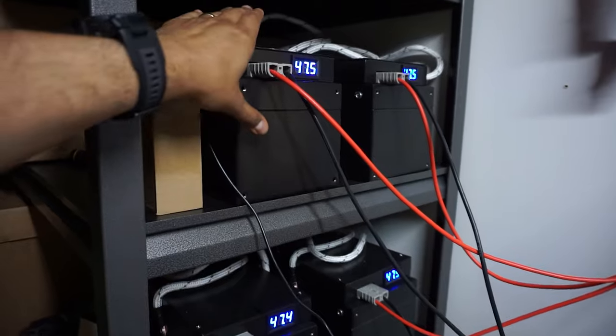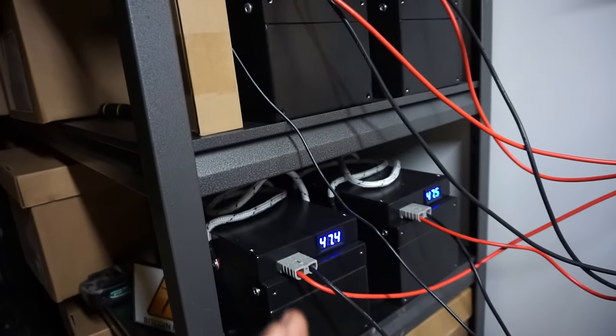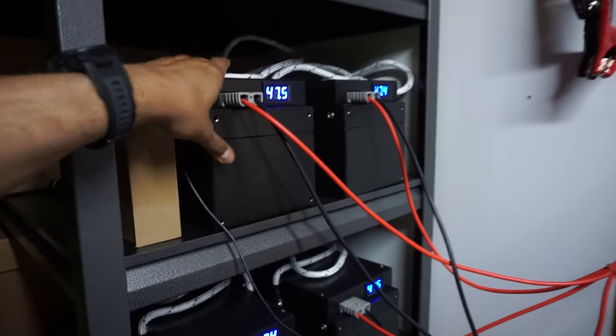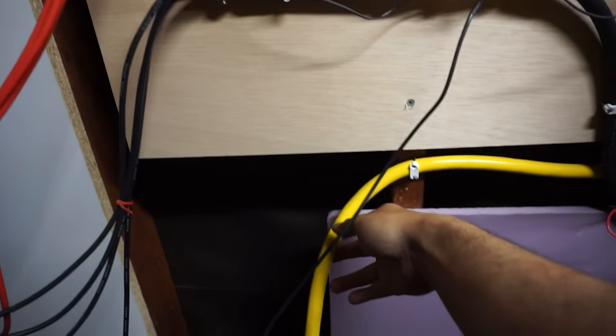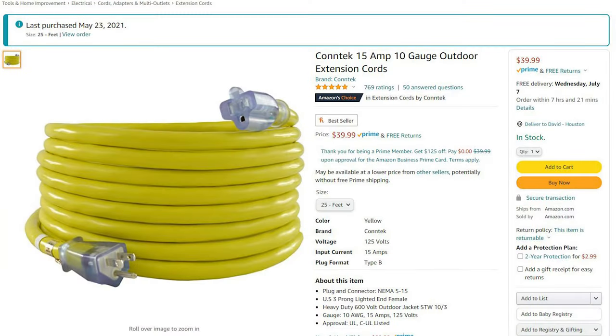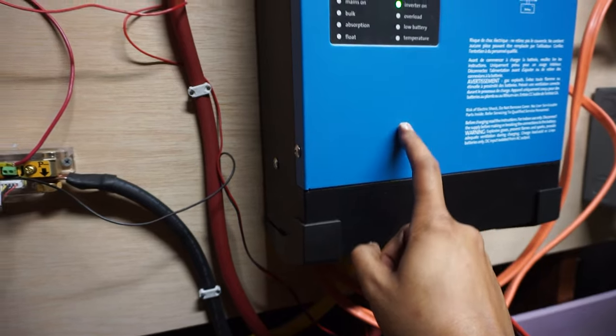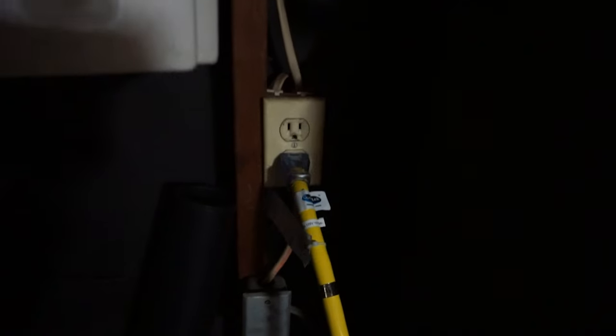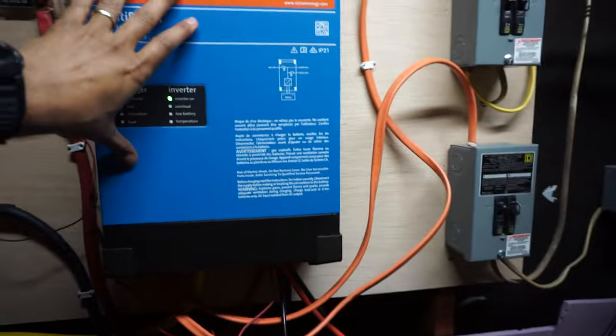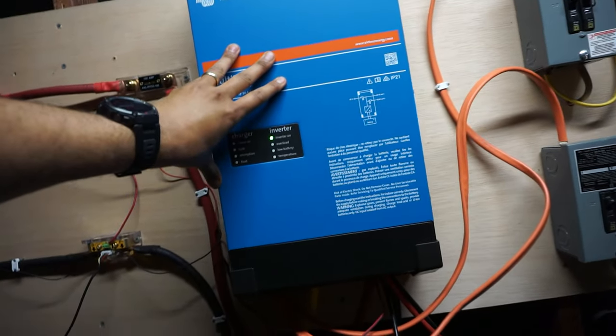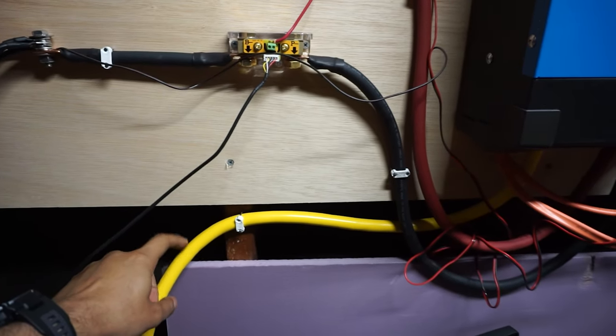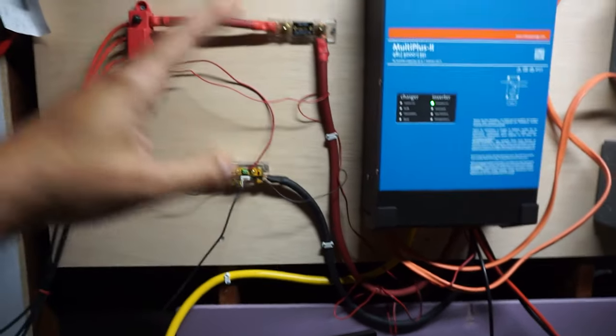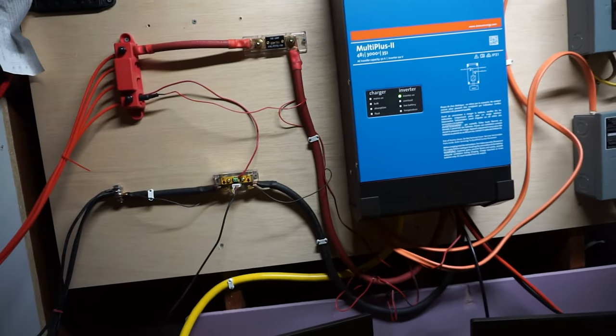These are small, easy to ship, not like the huge ones that have to go on a pallet and all that nonsense. So that's why I went with these. And so with the way the system works, here is a plug and this is an extension cord with the ends chopped off that goes into the Victron inverter here. And that just plugs into the wall, like no big deal. So what happens is this thing is set up to only draw a maximum of 13 amps from this cord here. And that 13 amps keeps me well below my 15 amp circuit that I have here.